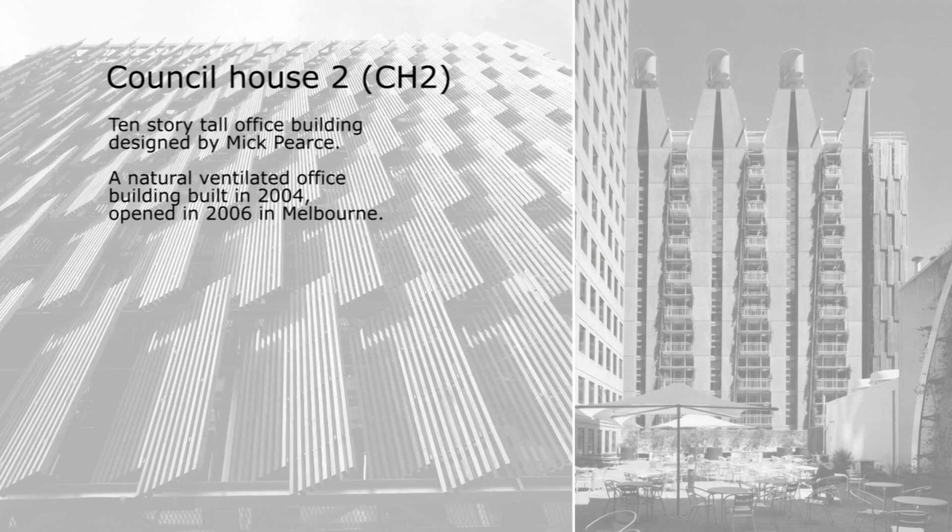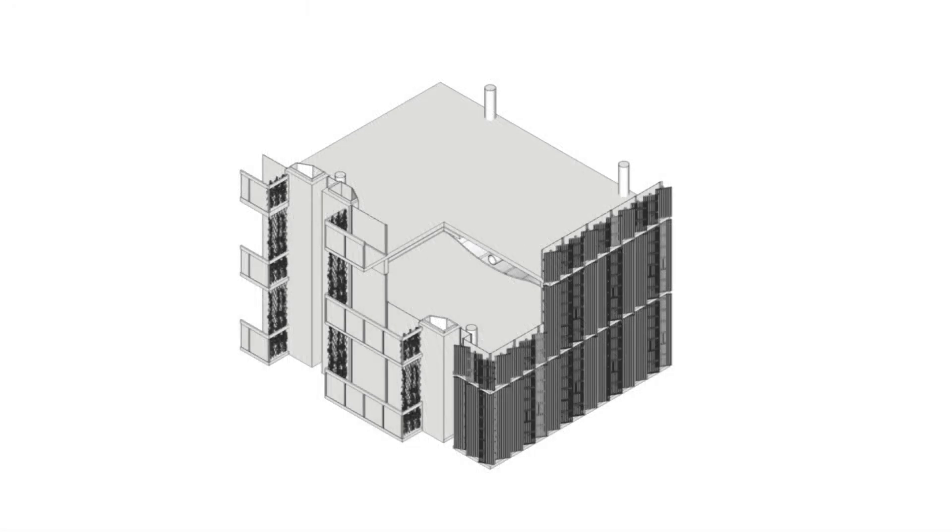The Council House 2 is a 10-story office building designed by Mick Pearce and opened in 2006. To prevent the building from overheating, moveable wooden lamella on the west facade and balconies on the north facade prevent direct sunlight from entering. Greenery prevents the sun from entering during the morning and evening. The ventilation system consists of solar chimneys in combination with vertical windmills. Fresh air enters the building from the cooler south facade, and excess heat produced during the day is stored in the concrete slabs hanging from the ceiling and can be released at night.